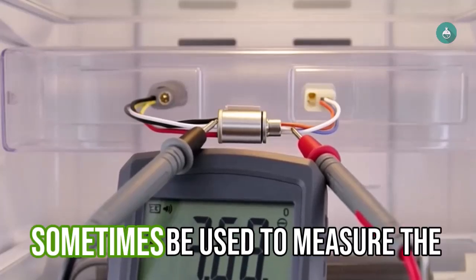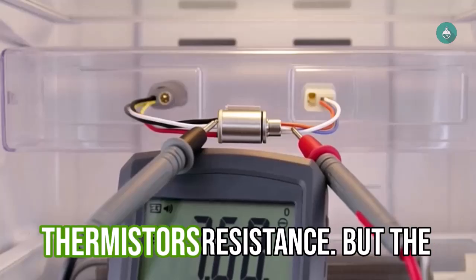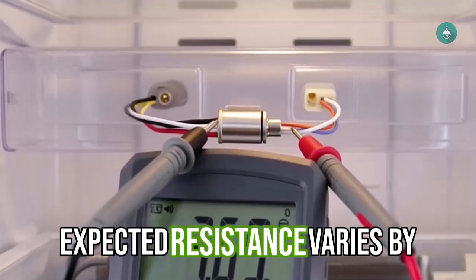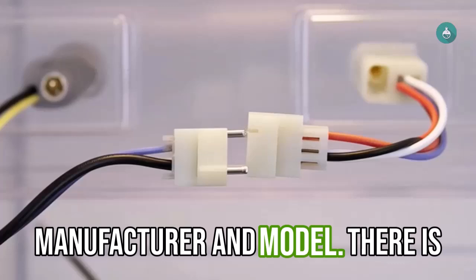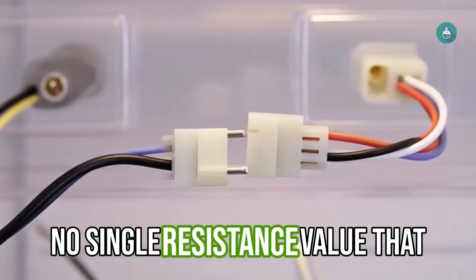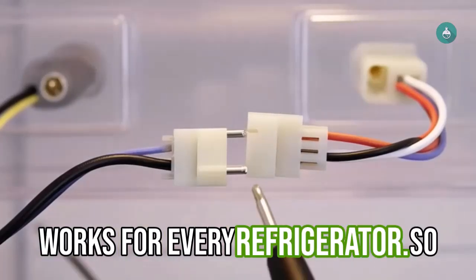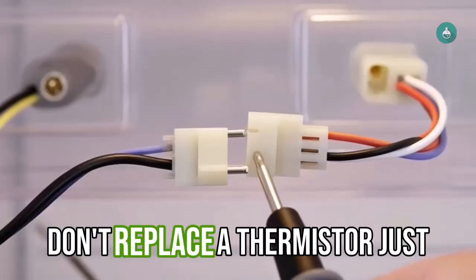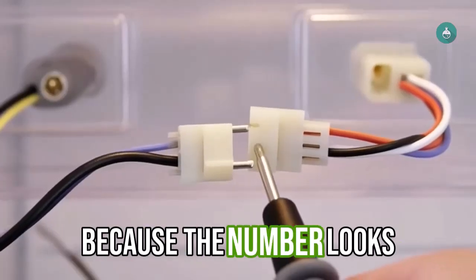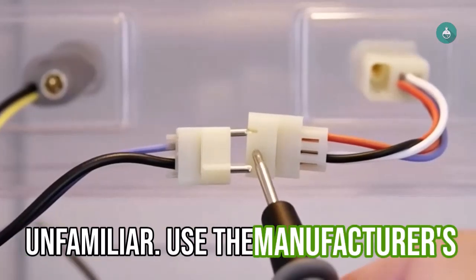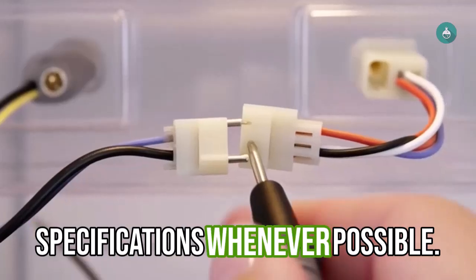A multimeter can sometimes be used to measure the thermistor's resistance, but the expected resistance varies by manufacturer and model. There is no single resistance value that works for every refrigerator. So don't replace a thermistor just because the number looks unfamiliar. Use the manufacturer's specifications whenever possible.